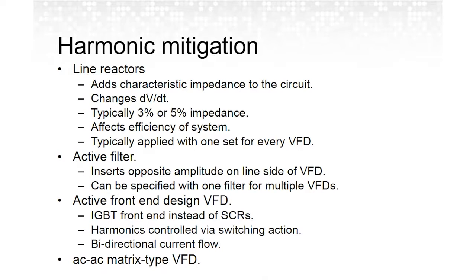The first one is line reactors, and these add a characteristic impedance to the circuit to sort of soften the change in voltage when the front end switches on that rectifier. Typically, the impedance of these line reactors is either 3 or 5%. And while they do reduce the amount of harmonic distortion, they also affect the efficiency of the system. They do dissipate power because of their characteristic impedance. And typically, you can't apply one set to multiple VFDs. You have to have a set per VFD.